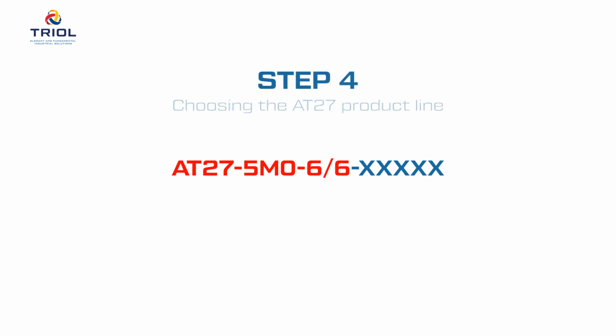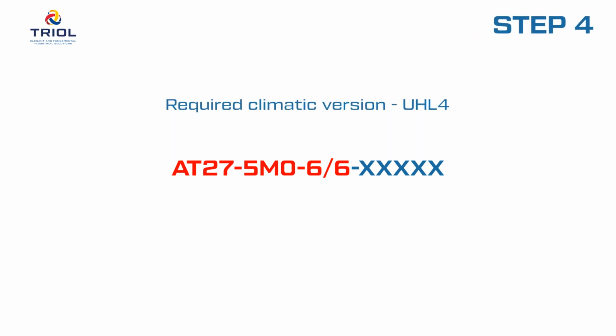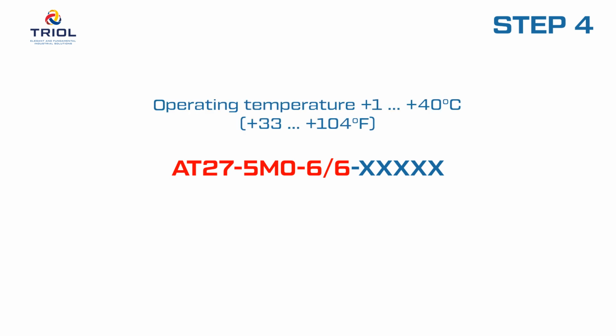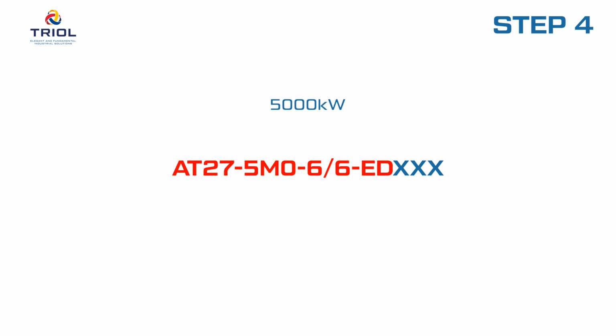Step 4. Choosing the AT27 product line. Required climatic version: UHL4, dry, heated, and ventilated room, operating temperature +1 to +40 degrees Celsius, which corresponds to the ED product line. We check the selected line according to the limits of the permissible active power of 5000 kilowatts for a given output voltage of 6000 volts. The selected power corresponds to the permissible power range for the selected product line.